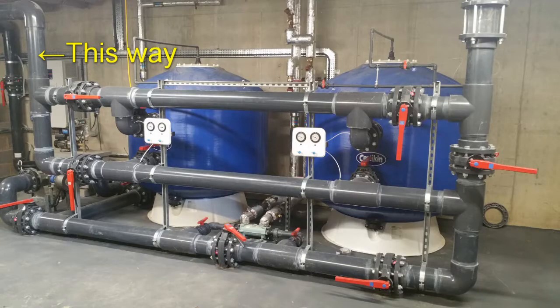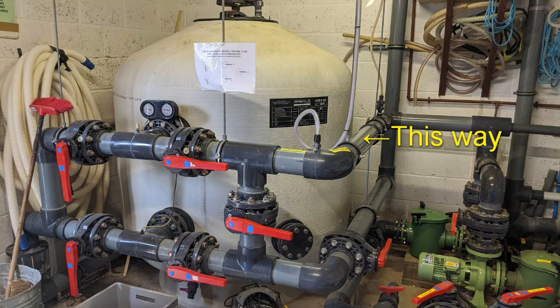Because what we're trying to find is that point where the water is coming into the plant room from the pool. So start moving backwards from the filter and follow the pipework all the way back, and then eventually you'll come upon the circulation pumps, or the filtration pumps they're sometimes called. These are the things that are making all the racket in the plant room. Because the water is always being pumped, it's being pushed through the filtration system. It's never being pulled through. In pool plant rooms, water is always being pushed through.